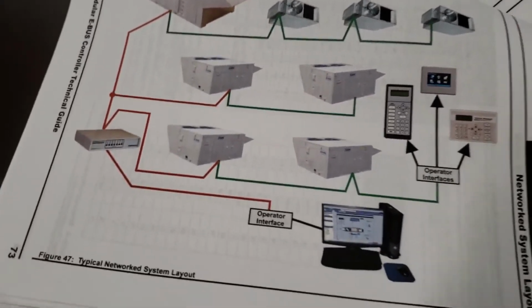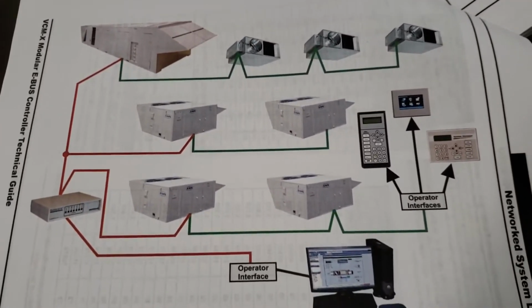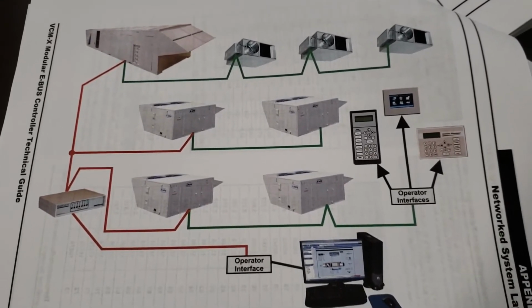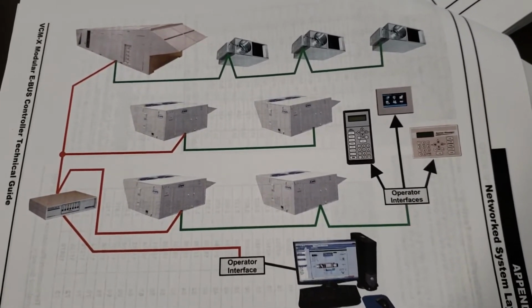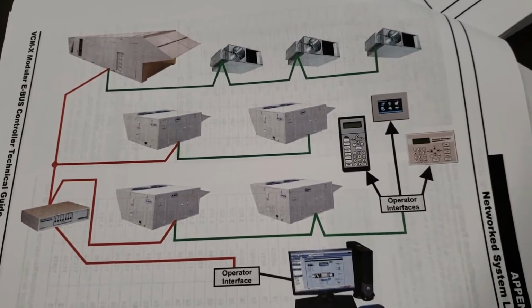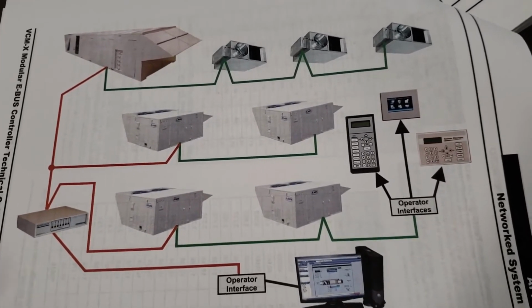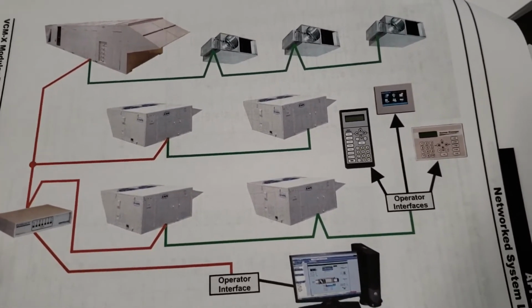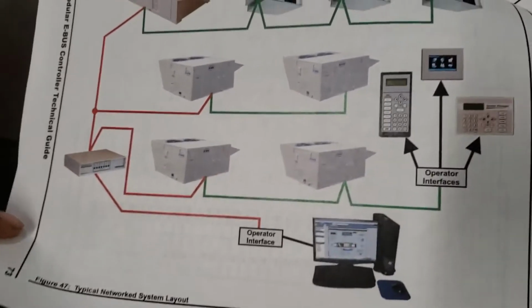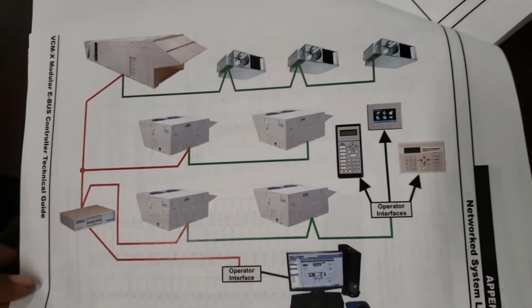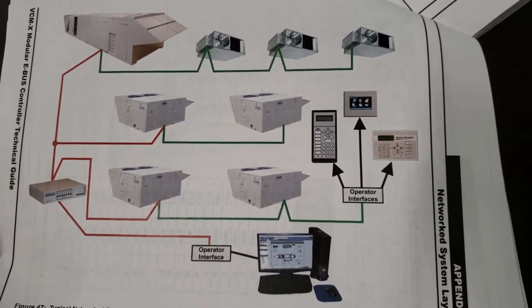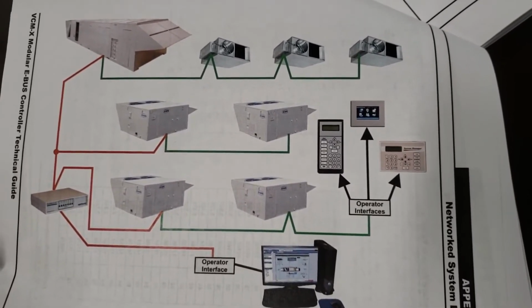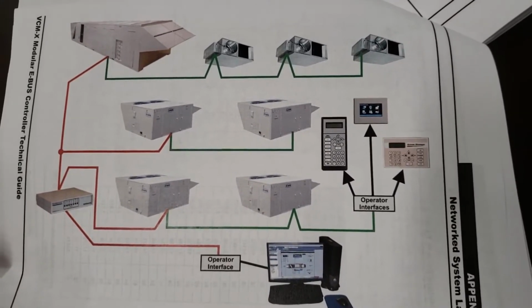This is what they call a network system. The green is representing the network loop, and the red is the local loop. Local loop is just like an interconnected system back to the controllers. And what they're not showing you is where these two come together, the red and the green. There's what they call a MiniLink polling device that captures the network loop and the local loop and separates them out.